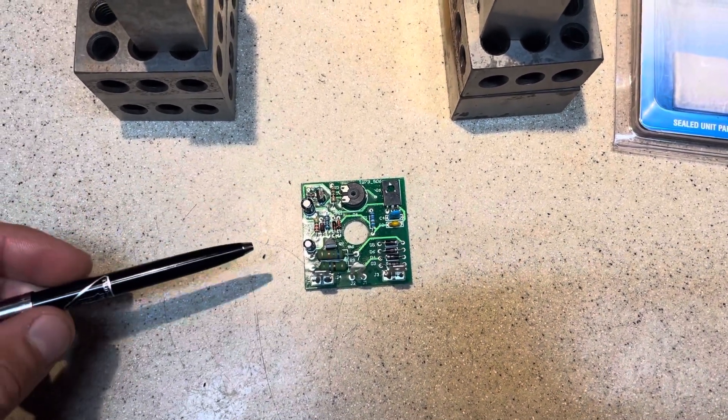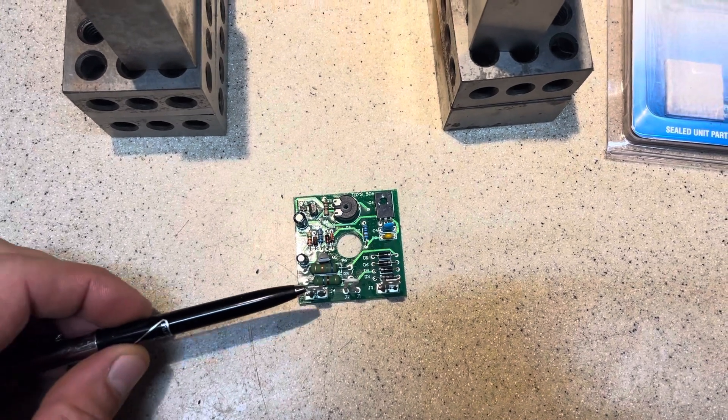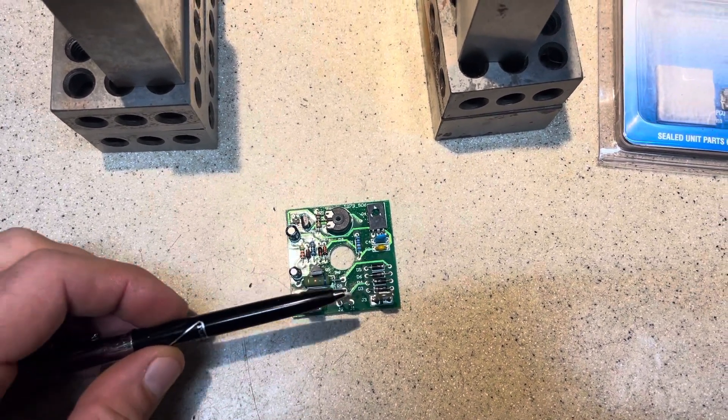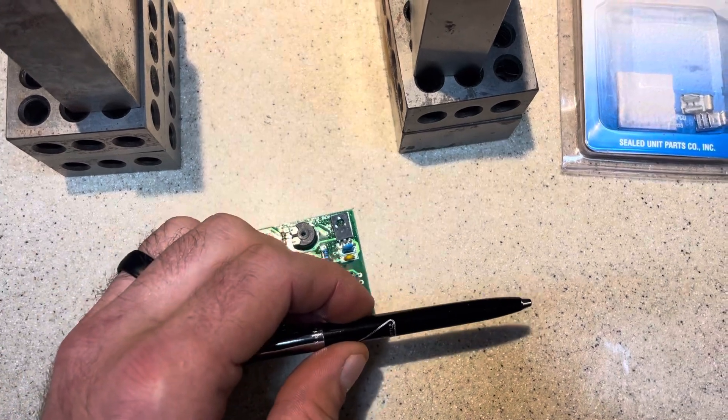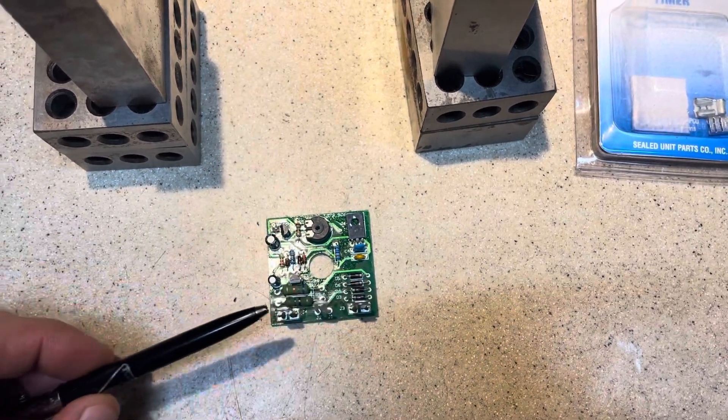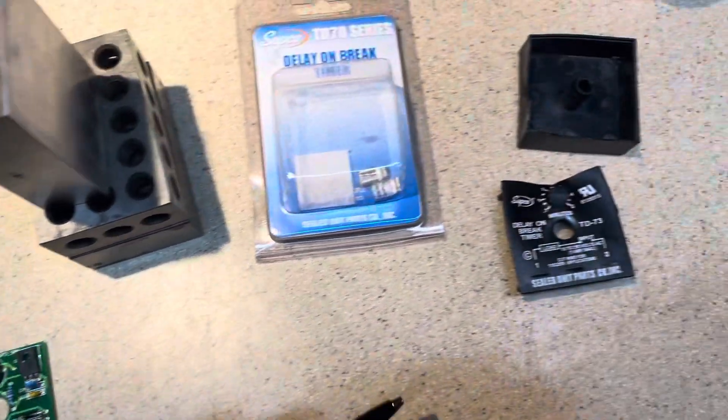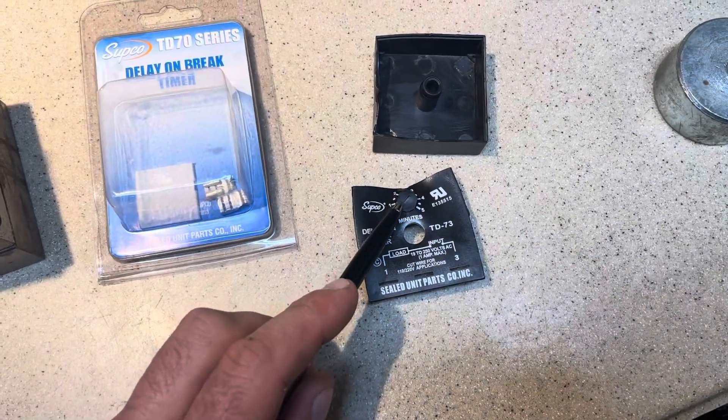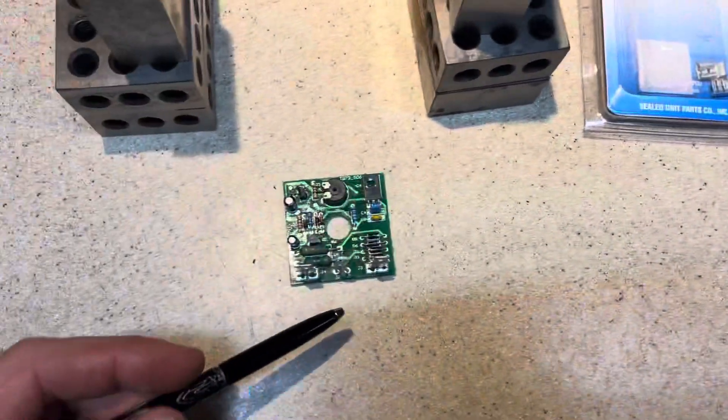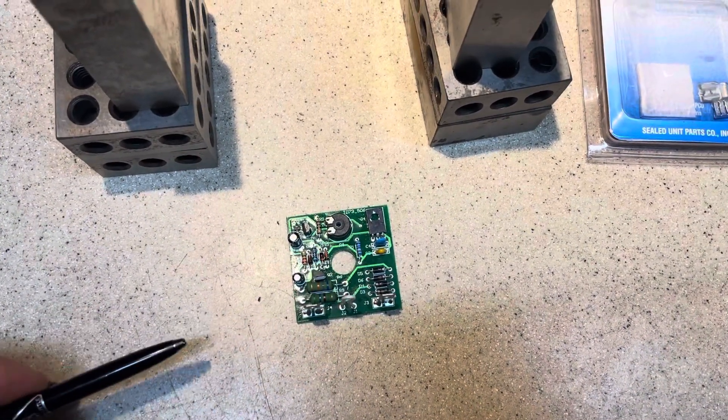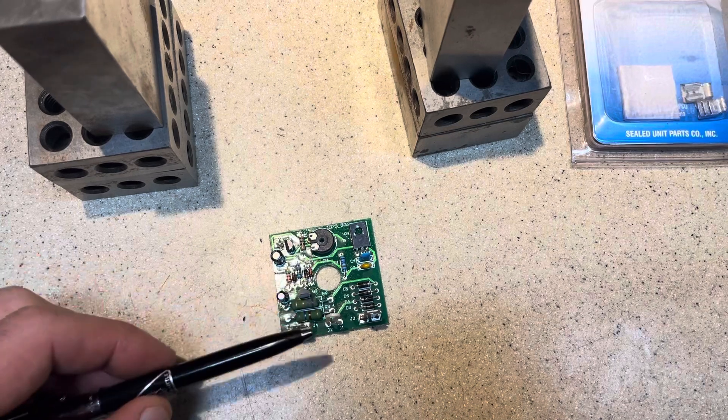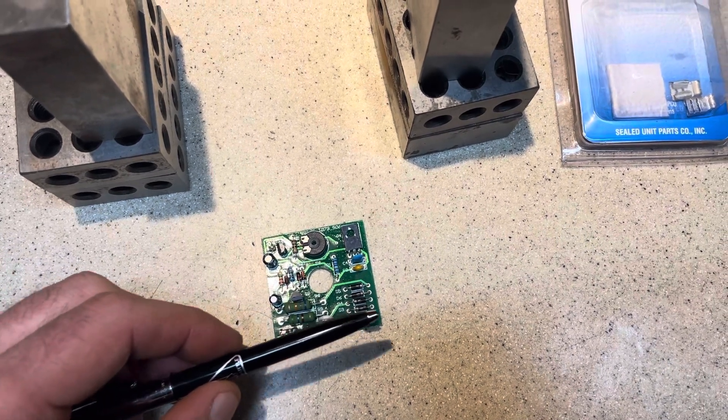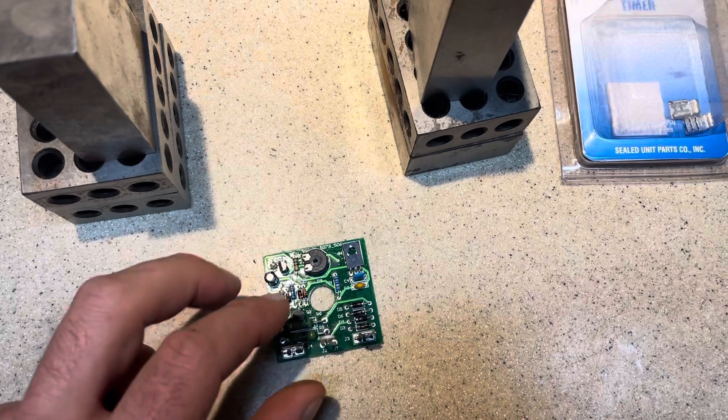So the way this works is your Y call comes in here and then normally just goes right back out to the contactor. But when the Y call ends, there is a period of time that you control with this knob where if Y comes back into here, the board will not allow it to go through until that time has expired.